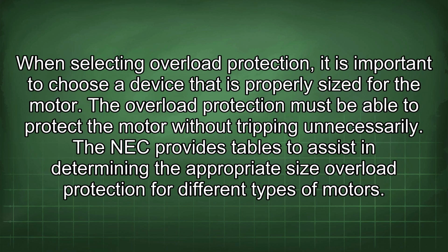When selecting overload protection, it is important to choose a device that is properly sized for the motor. The overload protection must be able to protect the motor without tripping unnecessarily. The NEC provides tables to assist in determining the appropriate size overload protection for different types of motors.